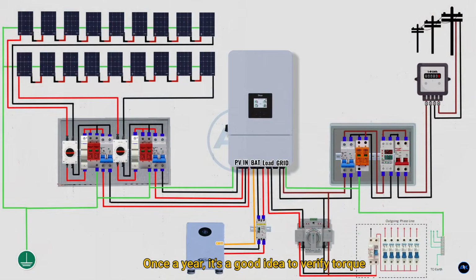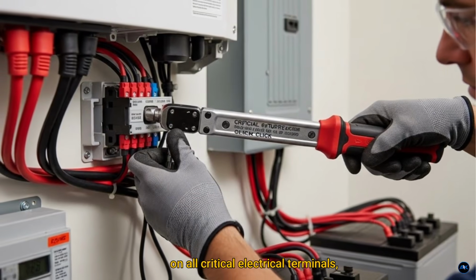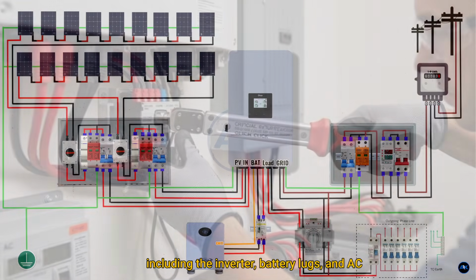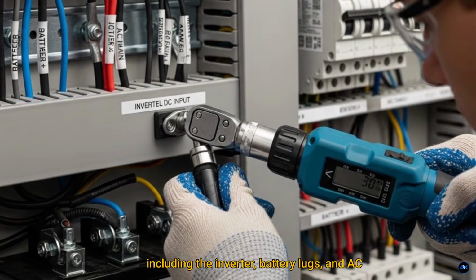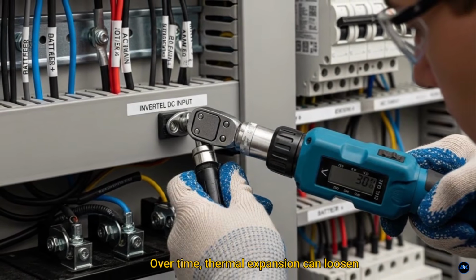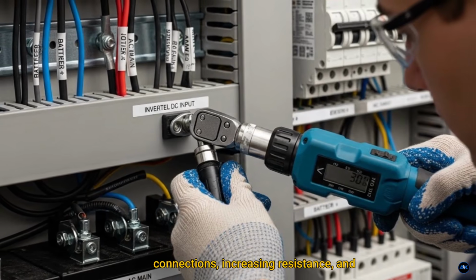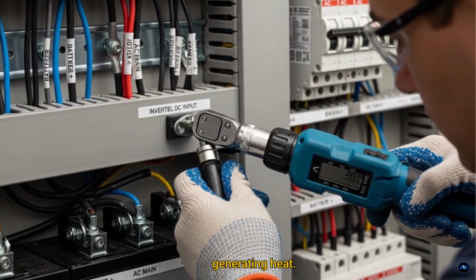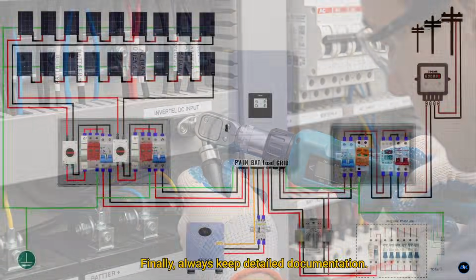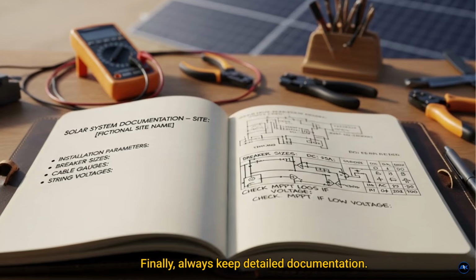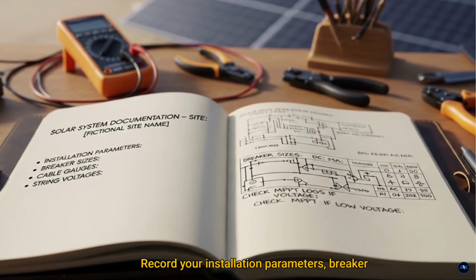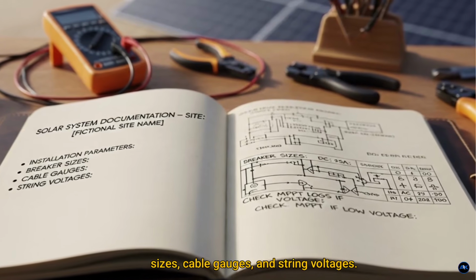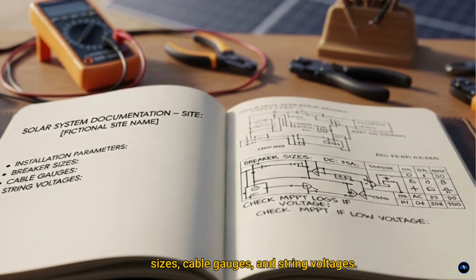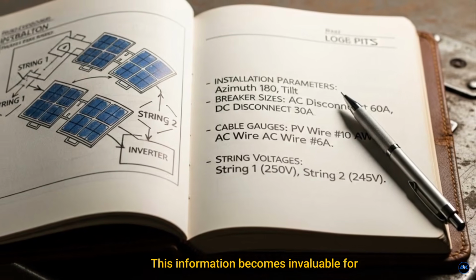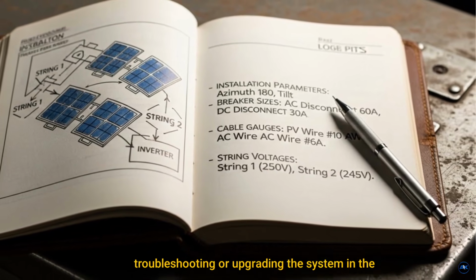Once a year, it's a good idea to verify torque on all critical electrical terminals, including the inverter, battery lugs, and AC breakers. Over time, thermal expansion can loosen connections, increasing resistance and generating heat. Finally, always keep detailed documentation. Record your installation parameters, breaker sizes, cable gauges, and string voltages. This information becomes invaluable for troubleshooting or upgrading the system in the future.